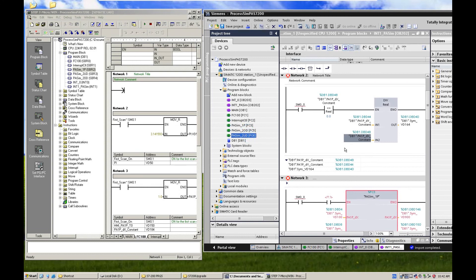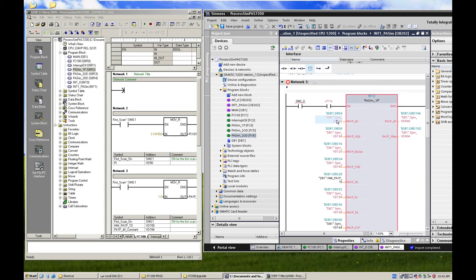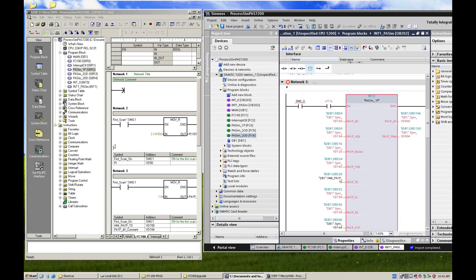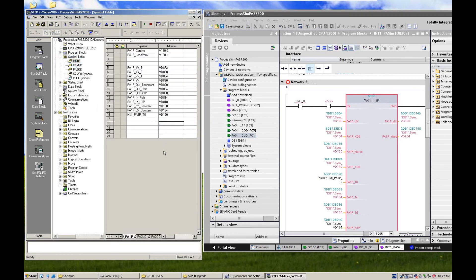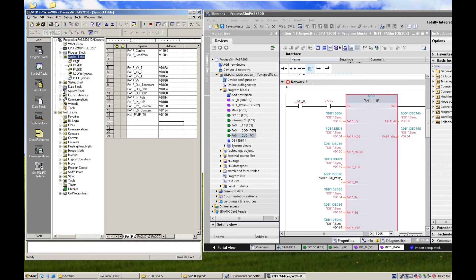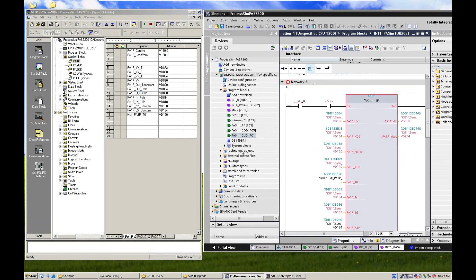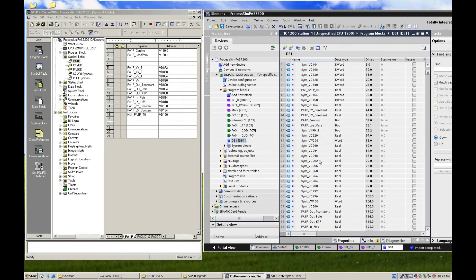But maybe the function changed because some tags like VD100 doesn't exist in TIA Portal platform. But if you replace to a memory address or DB address, it's very easy to replace. And another thing is, if we go to the symbol table in the S7-200, and this is the tag list in the S7-200 controller. And after the converted, under the TIA Portal platform, all those tags converted to a DB1 here, the data block here. So you can change the structure of the ladder logic.